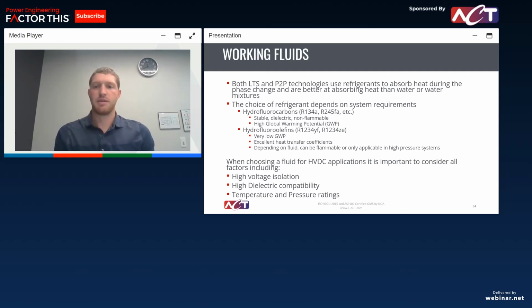So looking at working fluids, as we talked about, both loop thermosyphon and pump two-phase use refrigerants, which are dielectric. We're absorbing that heat during phase change, and they'll do that better than water mixtures, a lot of which are used in single phase. Two main types of refrigerant we'll use are hydrofluorocarbons and then HFOs. Hydrofluorocarbons are probably a lot of the refrigerants you've heard of, like R410 and R134A. They're stable, dielectric, and non-flammable, so they are a staple in most refrigeration systems you'll see, especially historical ones. They're very, very useful. The one drawback is they have high global warming potential. So we're seeing more and more in some applications that this is a concern, and some industries are moving away from those.